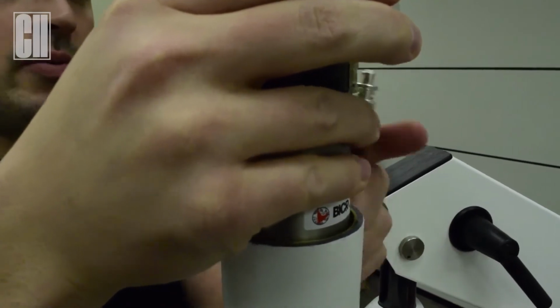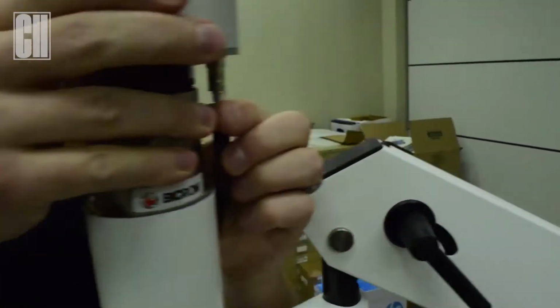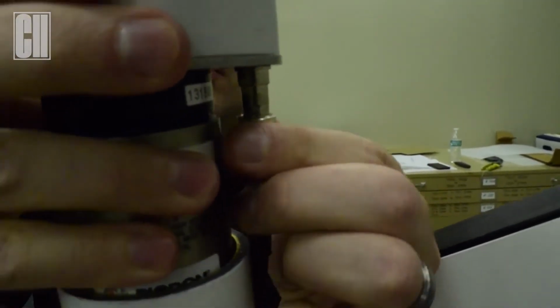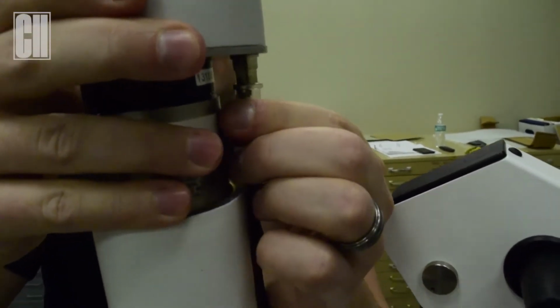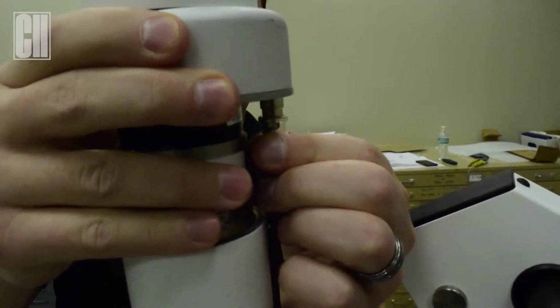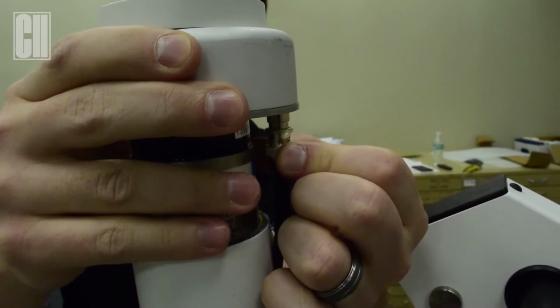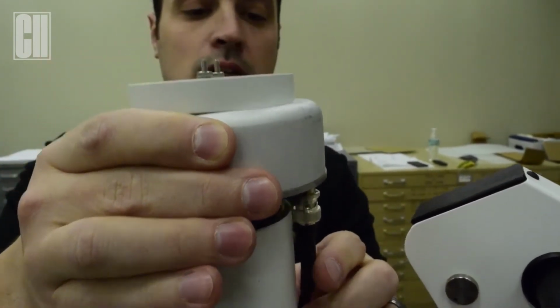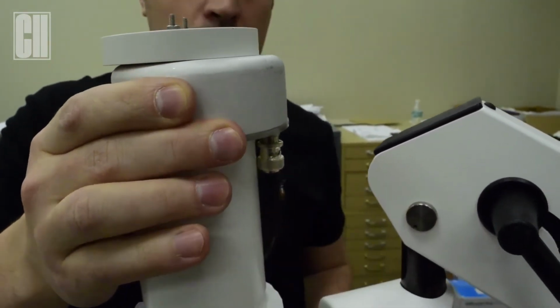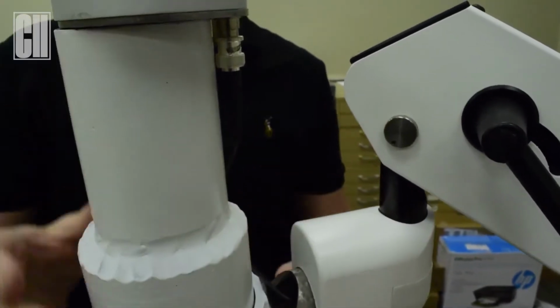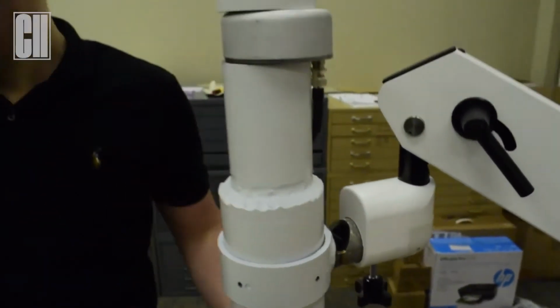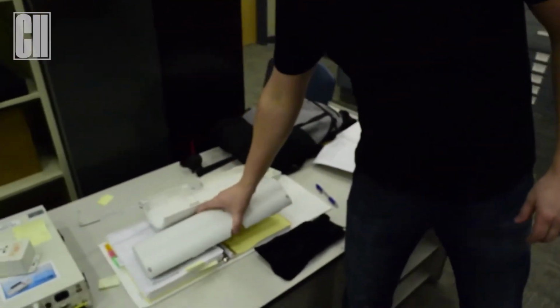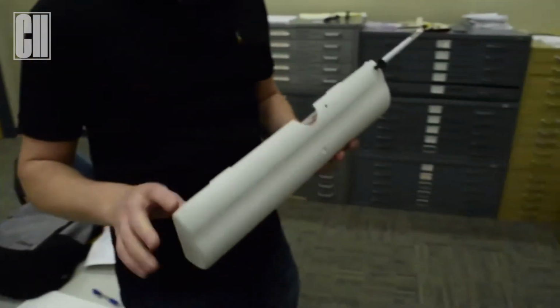Before you lower it to the bottom, you want to grab your probe cable, attach it to the connector, and it will key in. Line it up, and then you lock it into place. Once it's locked into place, you can lower it gently into the collimator. At this point, we can then put the casing back on.